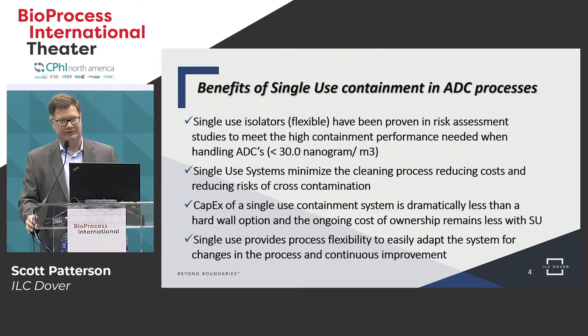By using a single-use system and reducing the cleaning process, we reduce the risk of cross-contamination. Also, the capital expenditure for doing isolation or containment of these small molecule payloads is much less when using a single-use type of product. The conventional stainless steel glass type of isolators cost hundreds of thousands of dollars to implement and deploy for these containment levels, where single-use systems are typically well under a hundred thousand dollars — often less than 20 percent of the capital expenditure cost of a hard wall type of device.